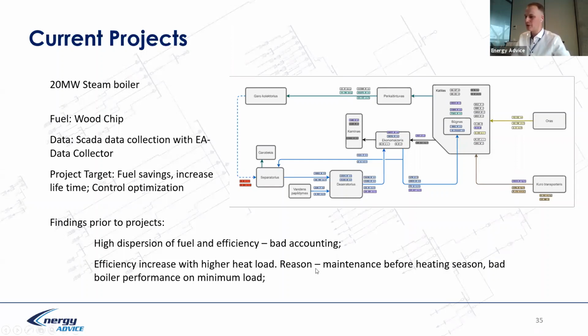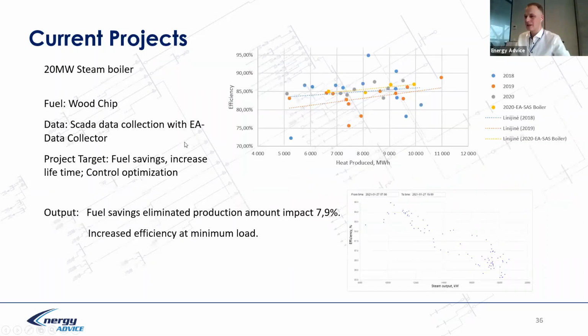Heat demand: the reason is probably maintenance before the heating season. We do maintenance before the heating season, which increases heat demand and probably increases efficiency, but not only. We detected bad boiler performance on minimum load. An example is the efficiency dependency on heat produced.